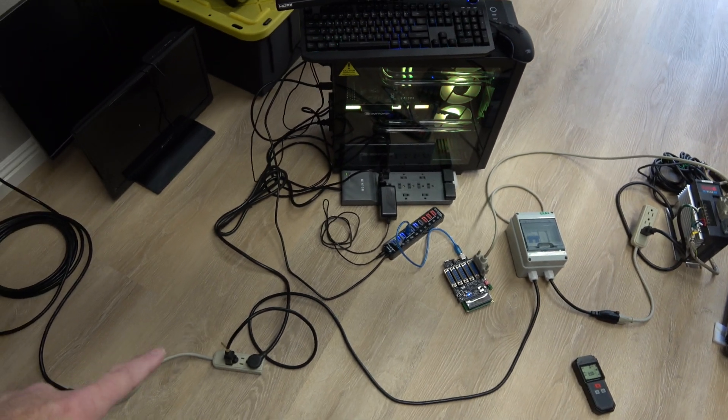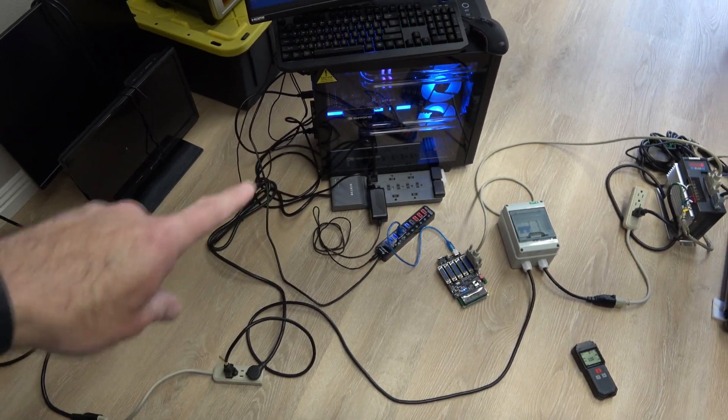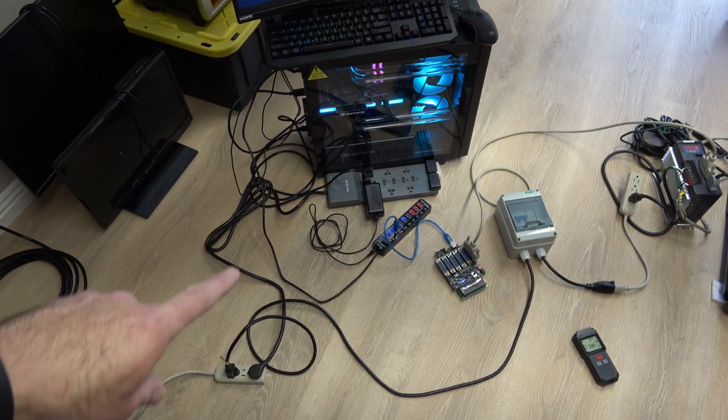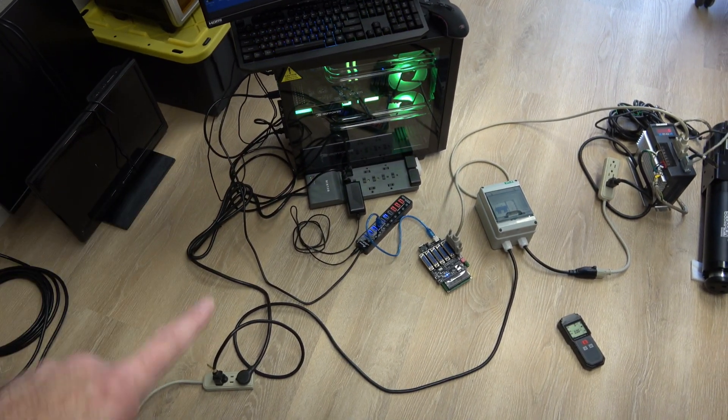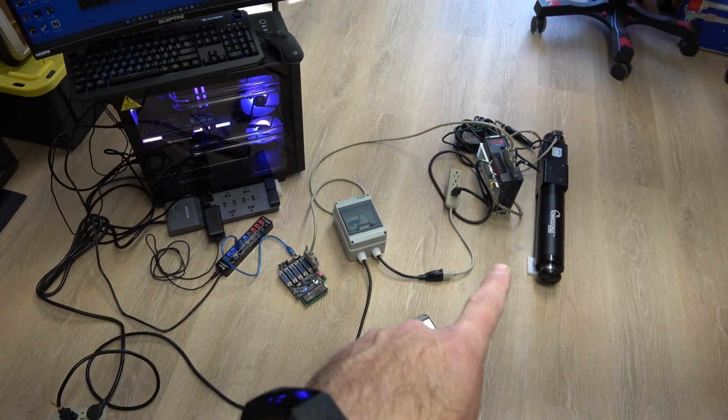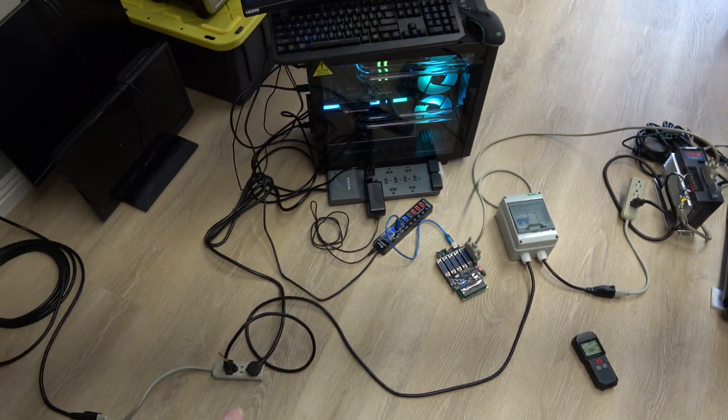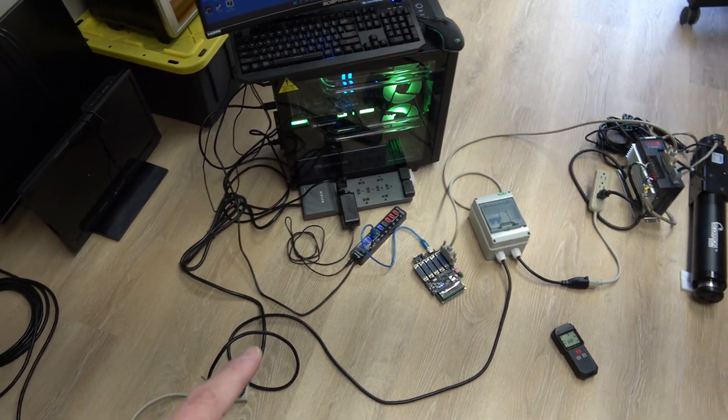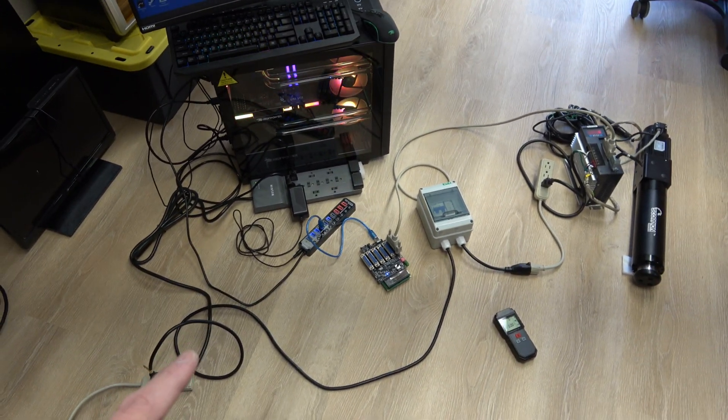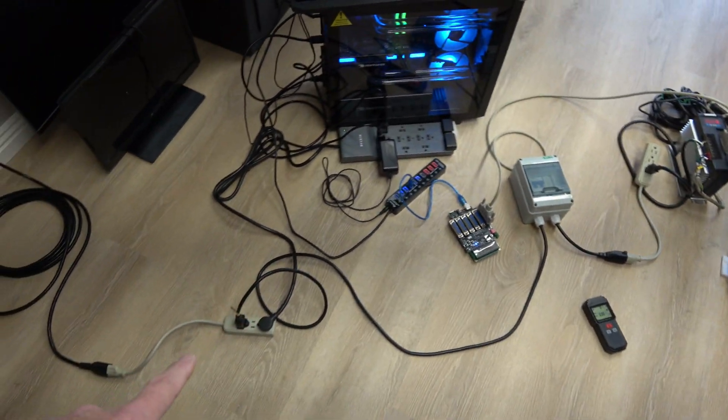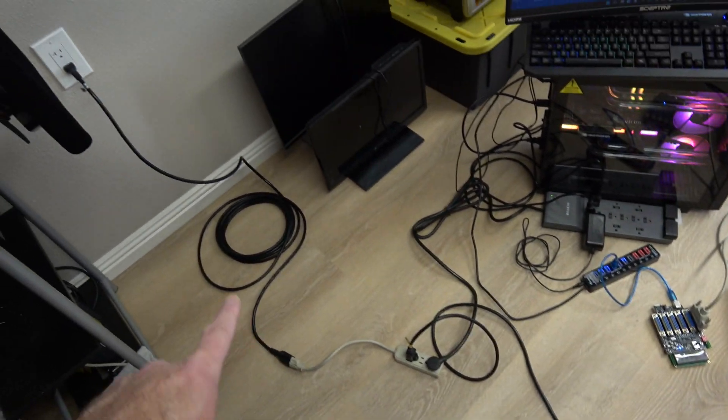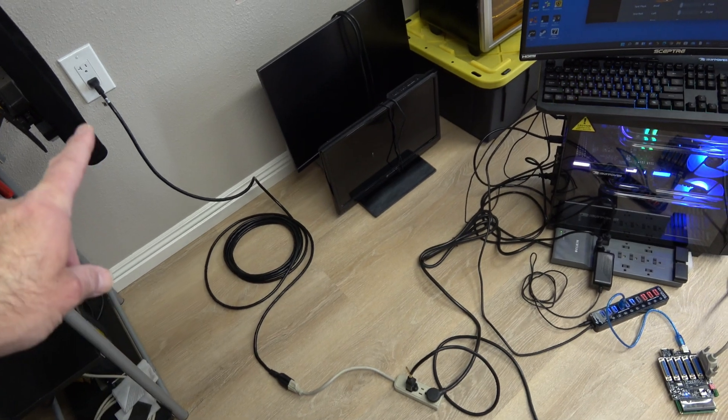Otherwise you should have everything like a star connection. The ground, one ground goes to the PC, one ground goes to the actuator, and this will be all in a single point. So you don't have ground loops.